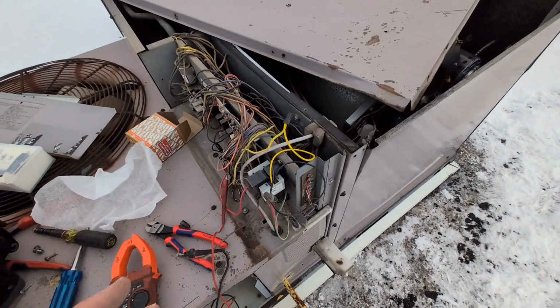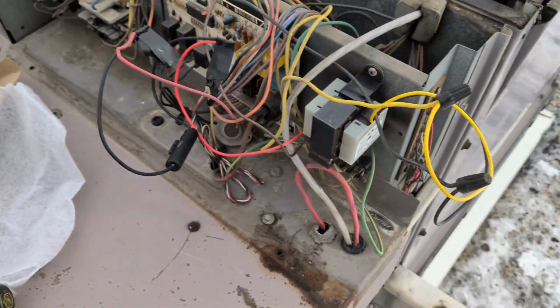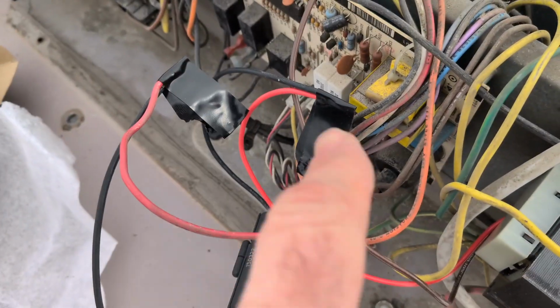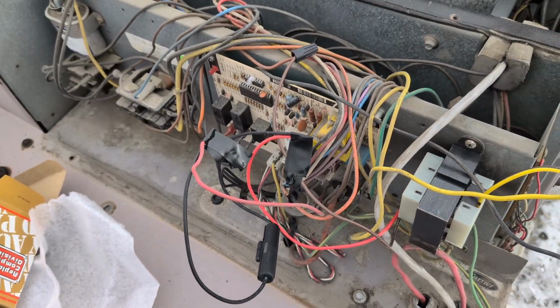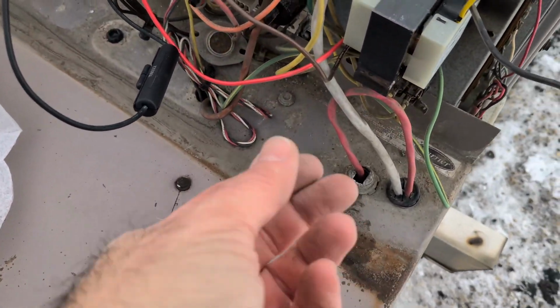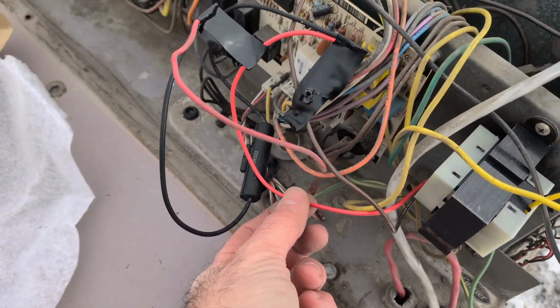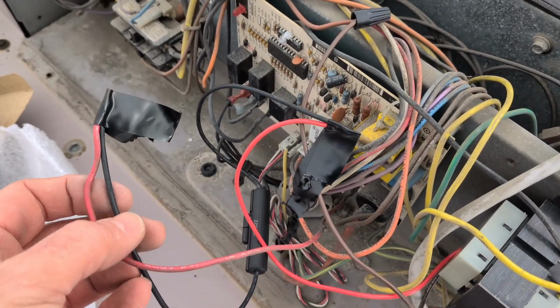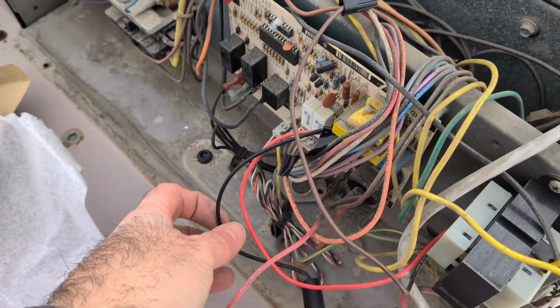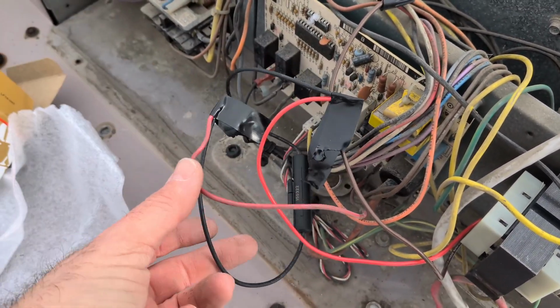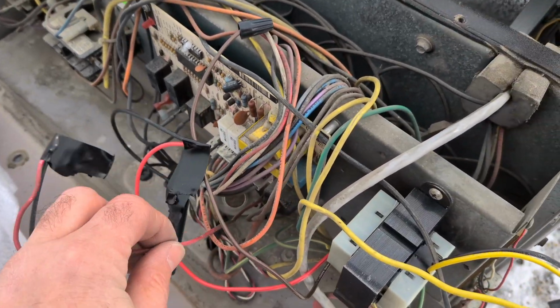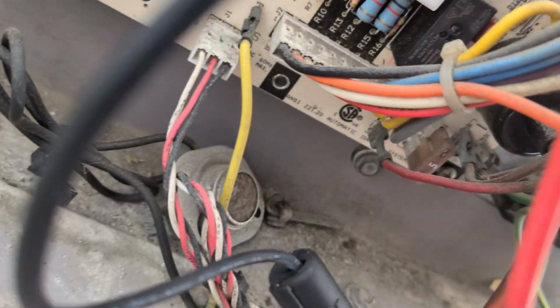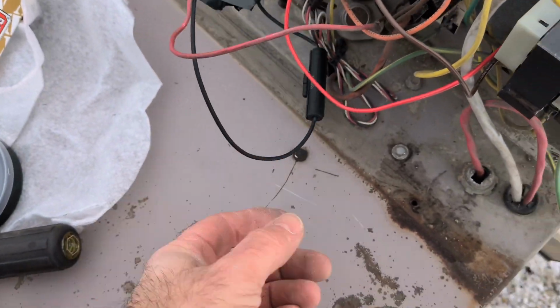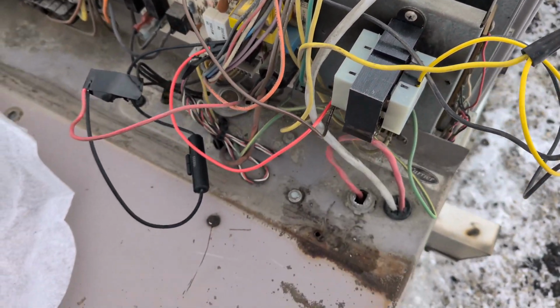So I'm going to show you what I mean by fusing it. So what you got to do here, I've just got these connections taped for now. I have to go back to the truck and get some wire nuts, but we're going to come out of the power side of the transformer. All right, we're going to go into the fuse holder, out of the fuse holder, and then we're going to the board right there. So this fuse is going to protect the transformer if there's a short somewhere else in the system.